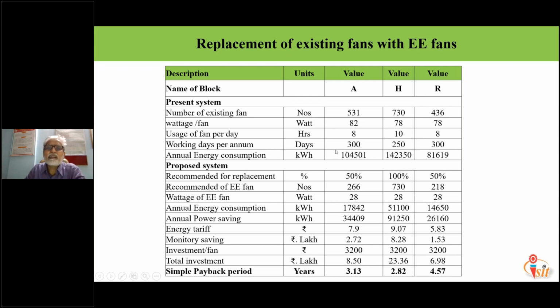On similar grounds, we have done the calculations and submitted the payback analysis. Here, the existing fans in that university number 531, wattage 82, usage approximately 8 hours, working days 300. We recommended them to replace 50%, which comes to 266, with energy efficient Gorilla fans manufactured by Atomberg, which is 28 watt.